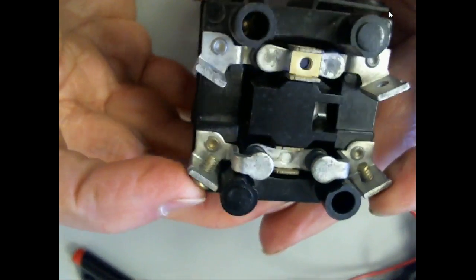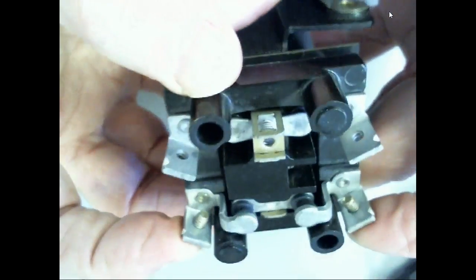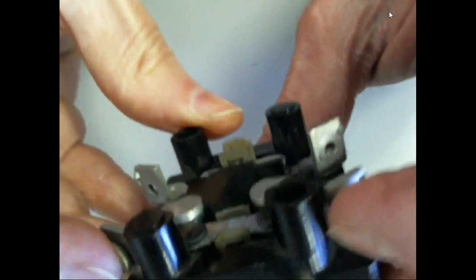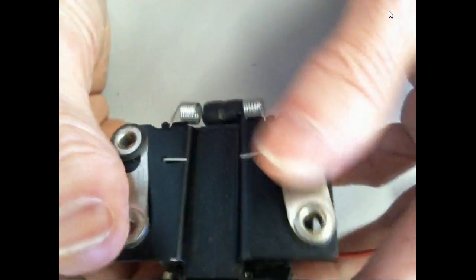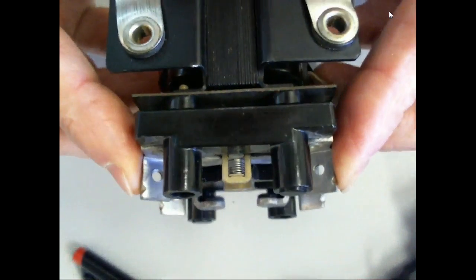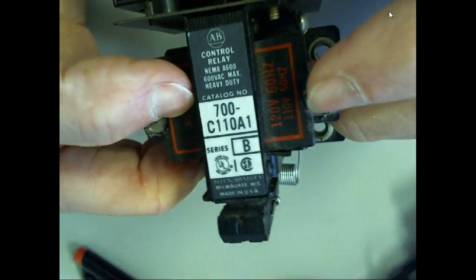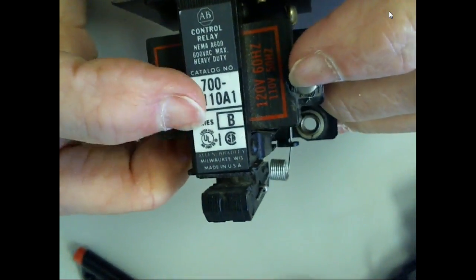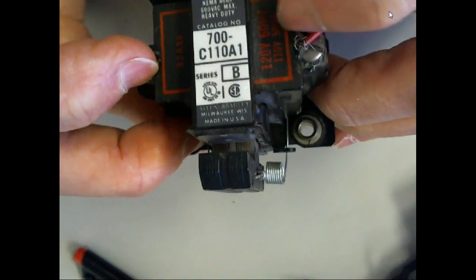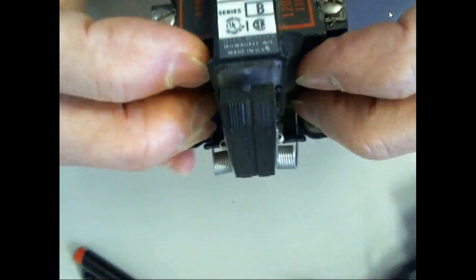These are where we'd make our connections to the contacts. Here would be two connections: this would be our electrical connection for the normally open, and this right here would be the two electrical connections for the normally closed. This right here would be where I'd make a connection to the coil, and this coil is rated at 120 volts, 60 hertz, so this is an AC relay.